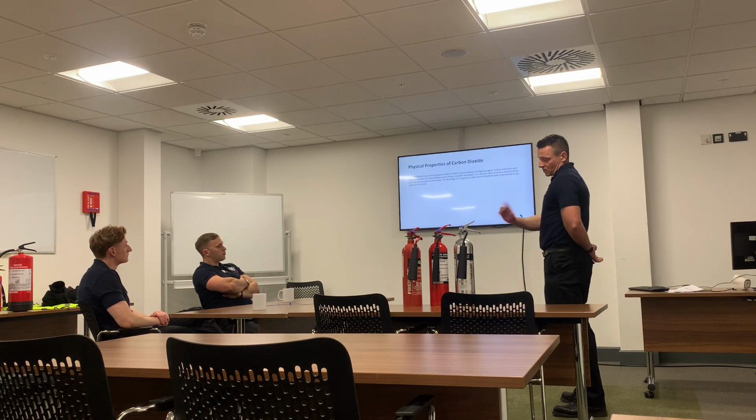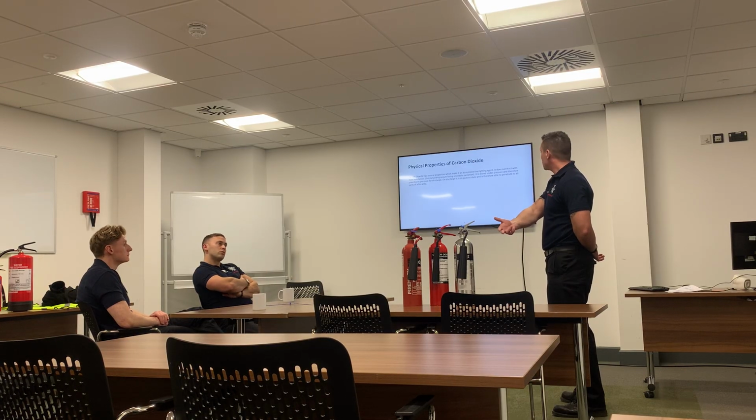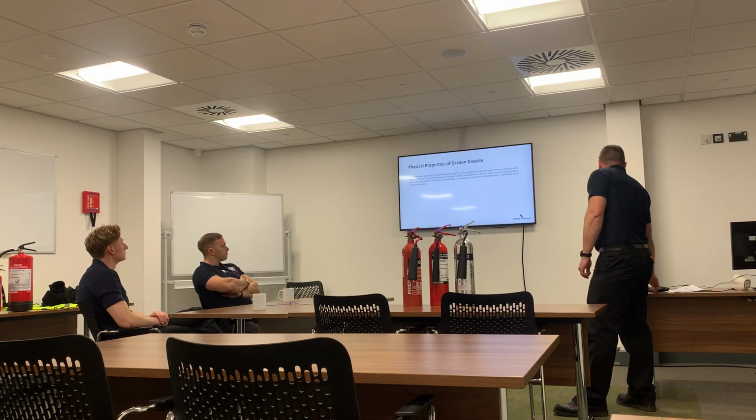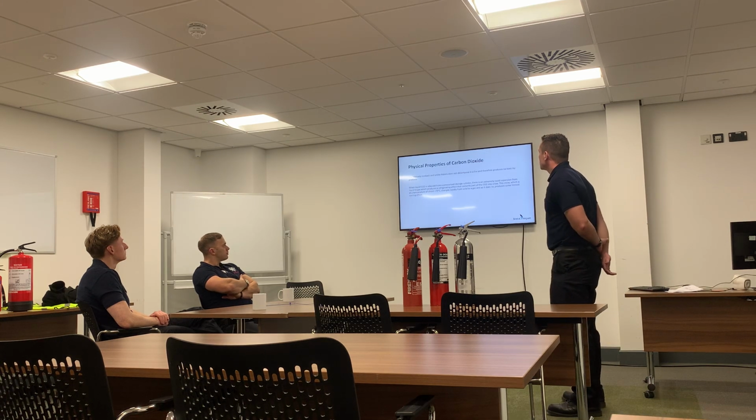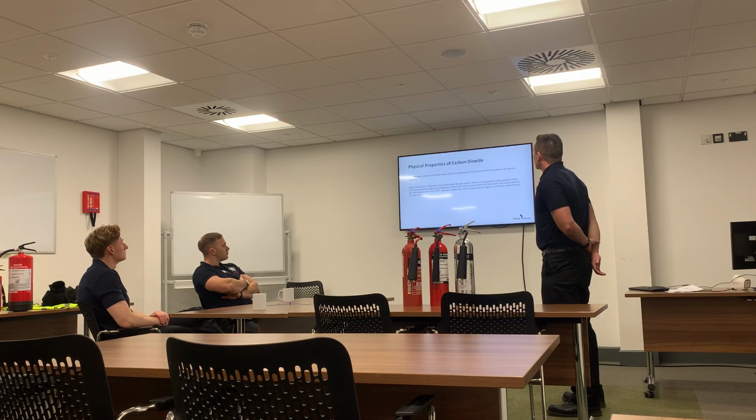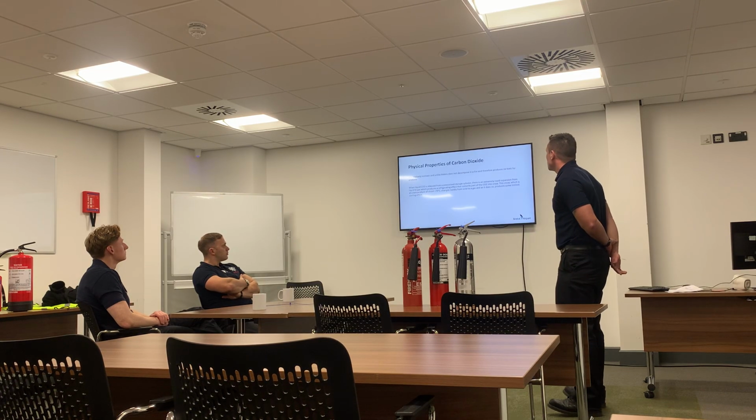So it's liquid CO2 within the extinguisher, and then the pressure is provided within the extinguisher. It then disperses out as a gas in a nutshell. Okay, and then furthermore on the physical properties. It is relatively non-toxic, and unlike halons, does not decompose in a fire and therefore produces no toxic byproducts.